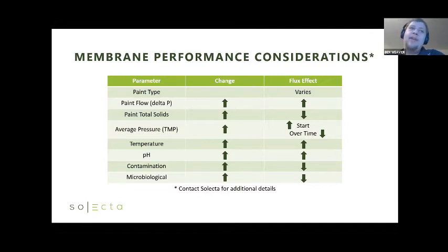It's due to the fact that we're introducing acid to control the foulance a little bit more. So, if we're looking at a clean membrane and you have it at pH 7 running water through it, if you increase that pH to 10, you're going to have a little bit more flow in a perfect situation. This doesn't take into account foulant interactions, which can impact the flux of the membrane.